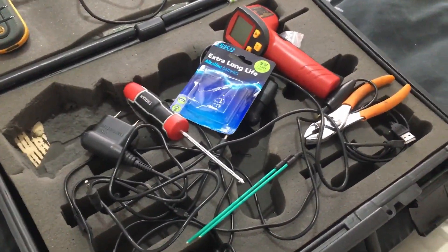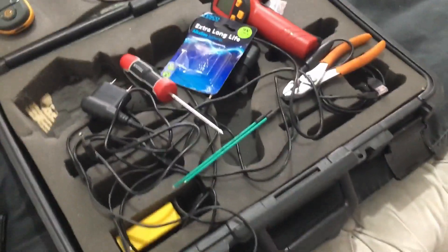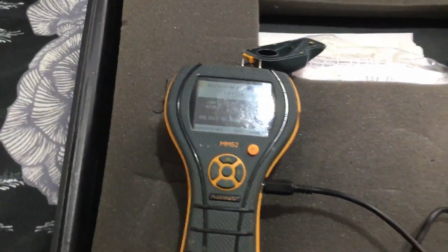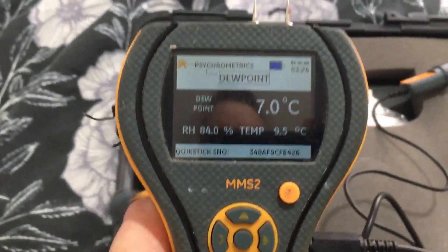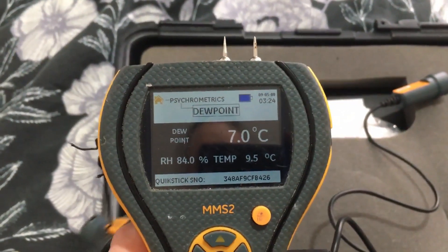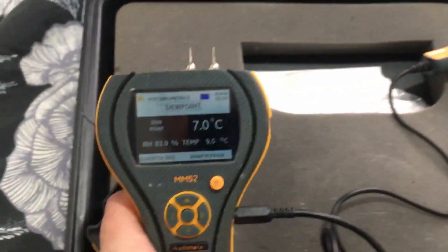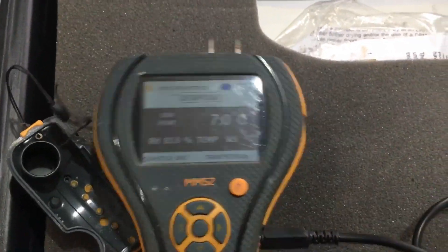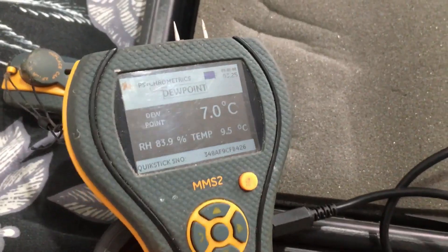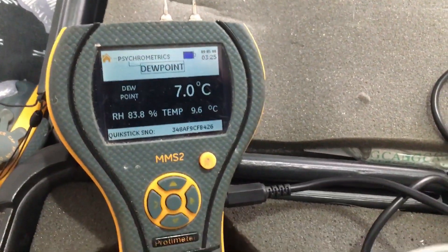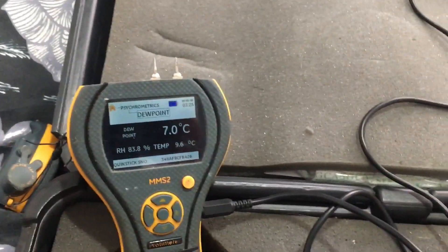So this is our box of magic tricks — it's all used equipment. Here's the first tool we use: the moisture meter. The first thing that's obvious here is the fact that it's only nine and a half degrees Celsius in here and there's a dew point of seven degrees. Basically, when any of the moist air strikes something at seven degrees Celsius or lower it actually reverts back to moisture.